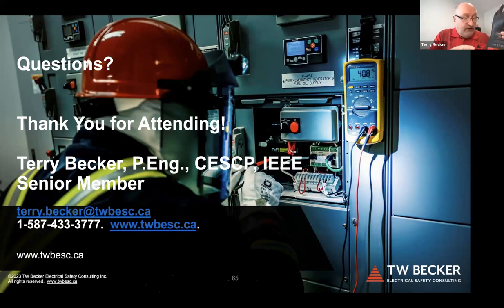So the gloves have to be tested, live line tools and hot sticks every 24 months, and temporary protective grounds every 36. Now that's the non-utility application of the hot sticks and the grounds. Electric utilities will test the rubber insulating gloves, hot sticks, and grounds more frequently because their power line technicians are using them daily, weekly. So the more frequently you use the shock PPE, then you might want to decrease an established policy of a minimum six month testing for the rubber insulating gloves.